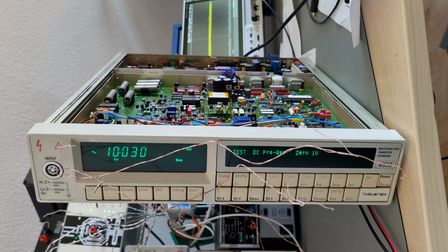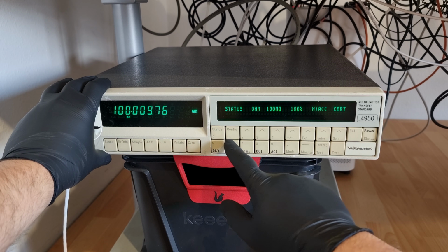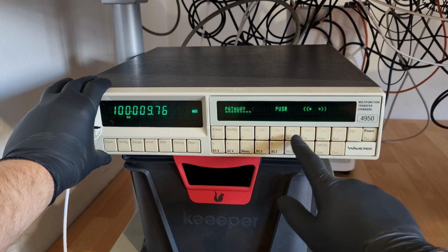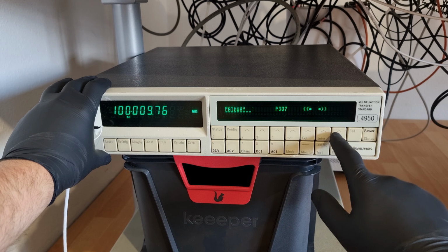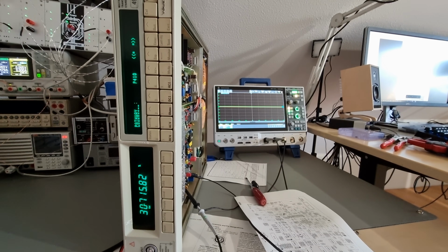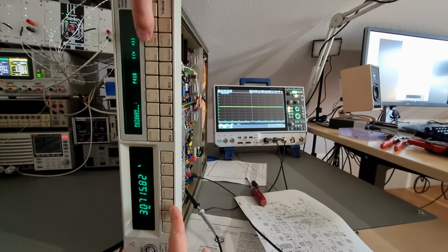The self-check program, aka confidence test, was a useful aid there. It's actually even more helpful than a sardonic display warning if it does encounter something out of the ordinary. This is well known for other Datrons from this era, but for this model as of yet undocumented. If it throws a fault at you, say 2500 AC system AC gain, you can use the secret cheat code status config3 to put the instrument in the same states in which the tests are performed. Such an investment of precious development time into methods that facilitate repair and troubleshooting would not fly today, that's for sure. It even lets you press the sample key to get ADC readings out of every one of these pathways.